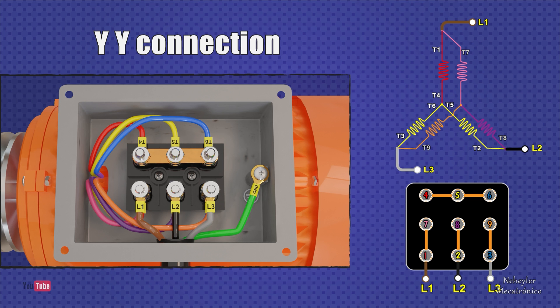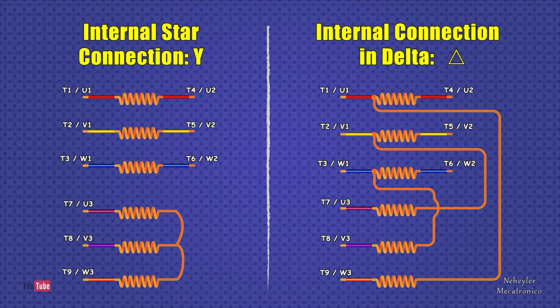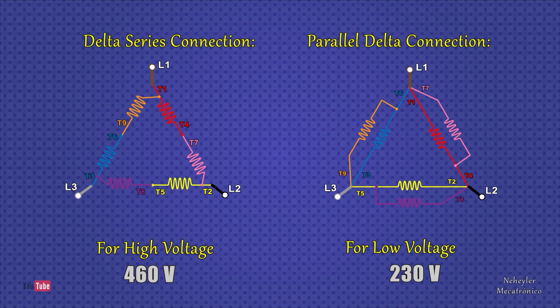So these two star type configurations that you just saw are used in medium and low power electric motors. If the electric motor is internally connected three of its terminals in delta or triangle, then the following types of connection can be made on its external terminals: series delta type connection for high voltage and parallel delta type connection for low voltage.